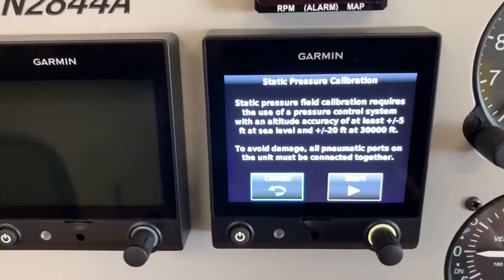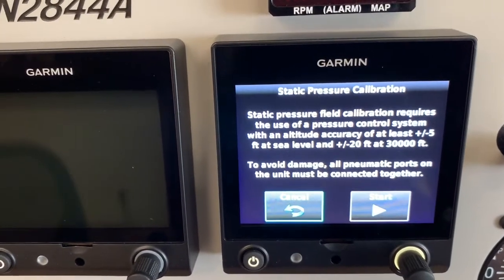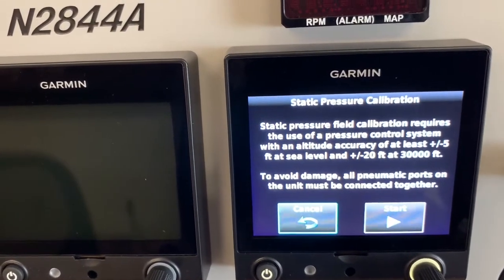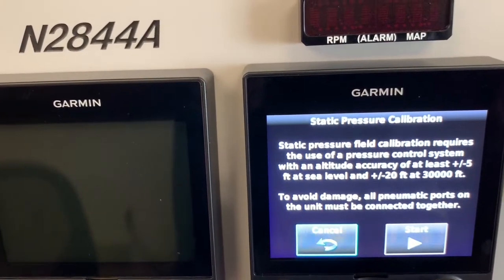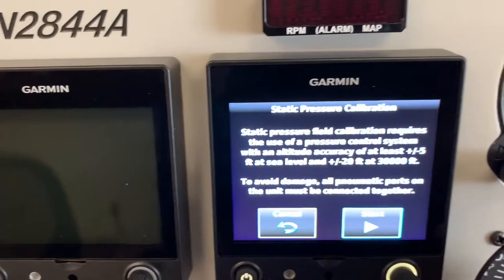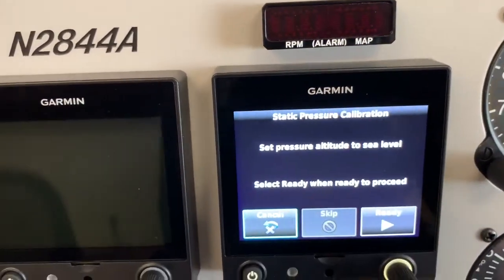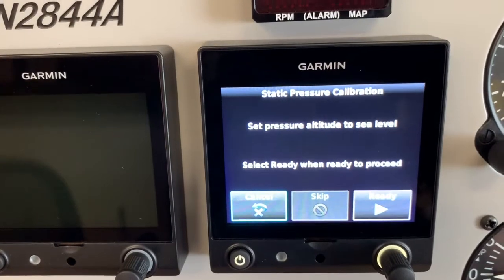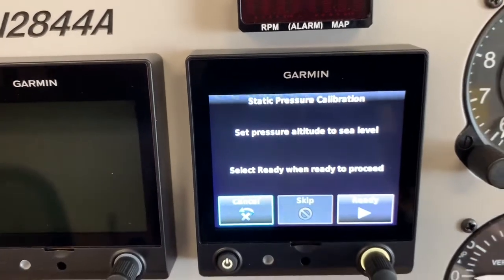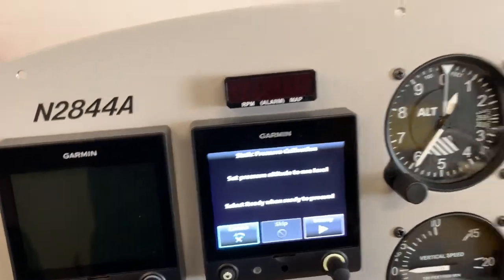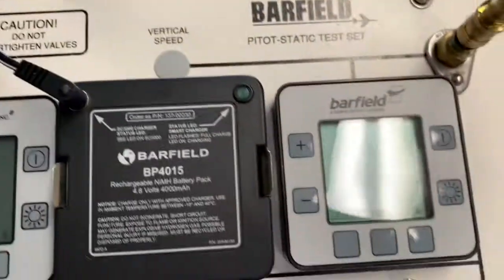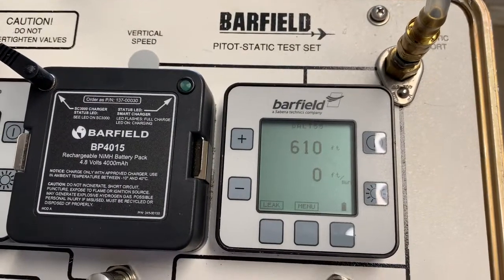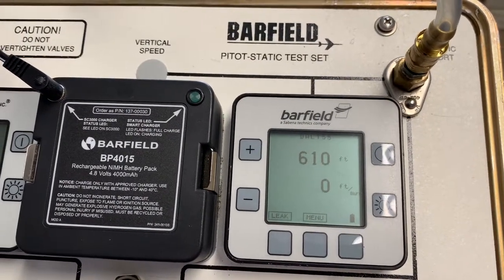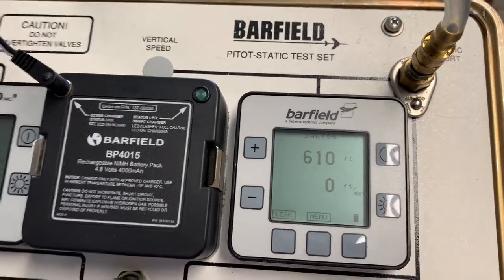You select OK, and then it'll tell you a warning there. I'm just letting you read it. And we meet those requirements with a test set. So we go to Start. Okay, we're going to do this up to 20,000 feet. So the first step is to set the pressure altitude to sea level. Okay, let's go over to our test set here. There's a glare. And we're at 610 feet. So we need to add some pressure to the system to simulate sea level.